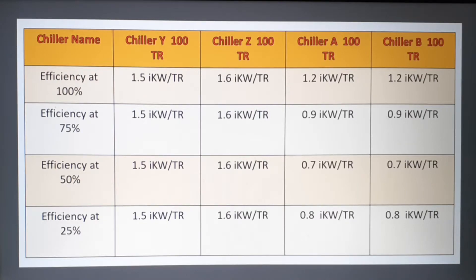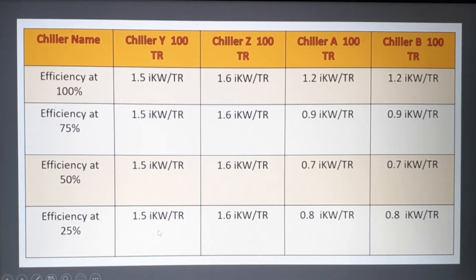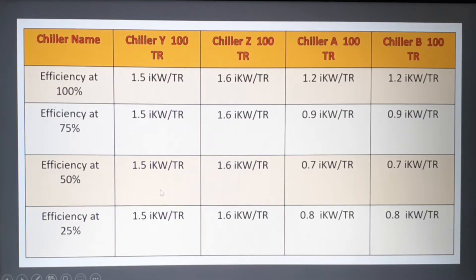People often get confused about what part-load efficiency means. It is simple: if you look at chiller Y and Z, the kW per TR is very constant across all different loading profiles. For chiller Y it is 1.5 kW per TR, and for chiller Z it is 1.6 kW per TR — constant regardless of load.